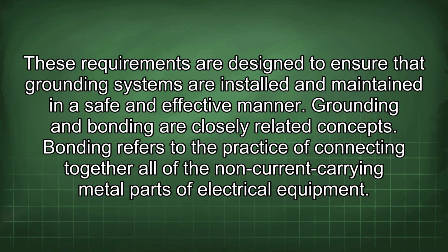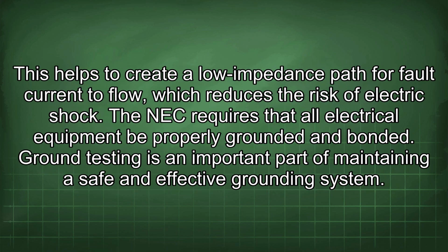These requirements are designed to ensure that grounding systems are installed and maintained in a safe and effective manner. Grounding and bonding are closely related concepts. Bonding refers to the practice of connecting together all of the non-current carrying metal parts of electrical equipment. This helps to create a low impedance path for fault current to flow, which reduces the risk of electric shock. The NEC requires that all electrical equipment be properly grounded and bonded.